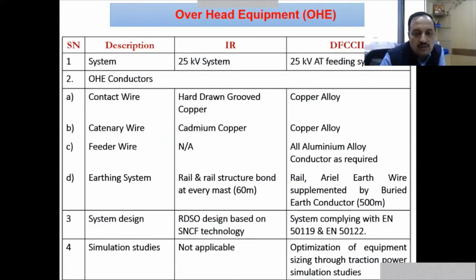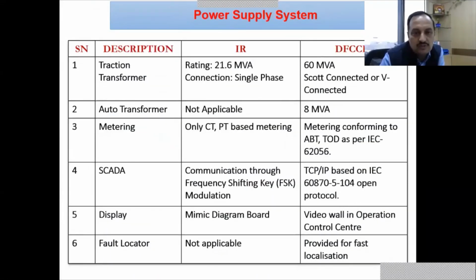Simulation study is not applicable in Indian Railways because the items are already standardized by RDSO, but here we have optimized the sizing of equipment based on the simulation studies. The traction transformer rating is 21.6 against 60 MVA here, which means around 3 times the rating of the transformer. We have used 8 MVA auto transformer, not used in IR.